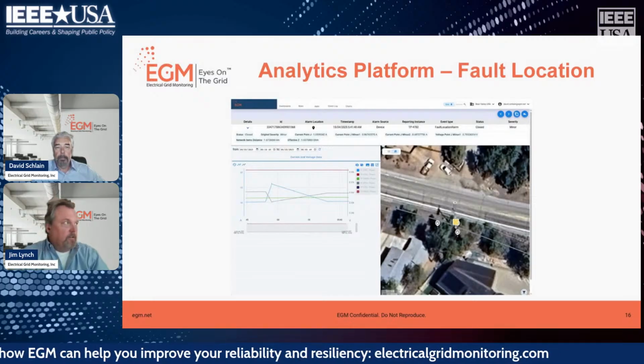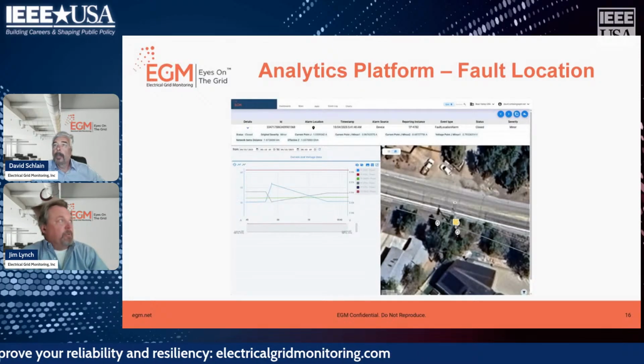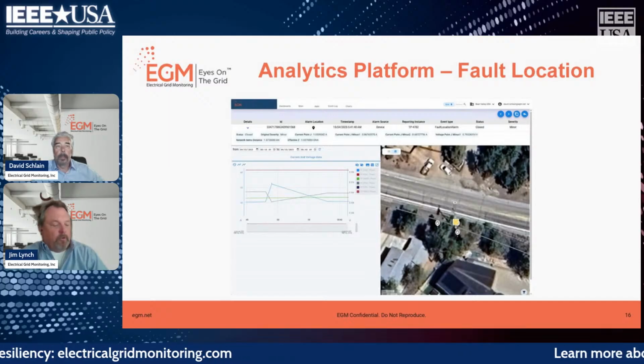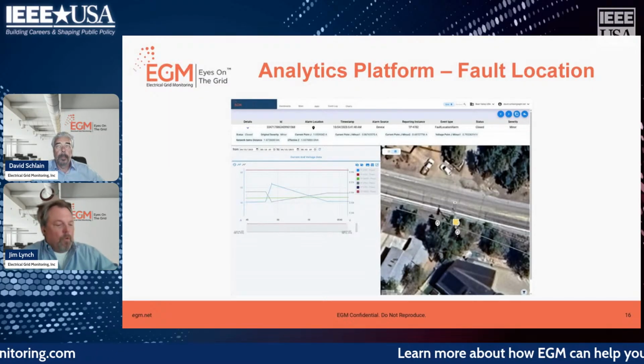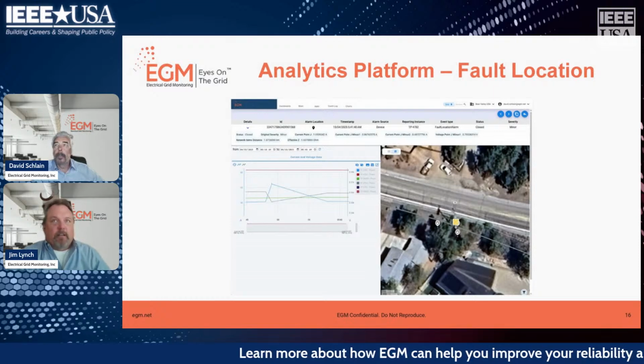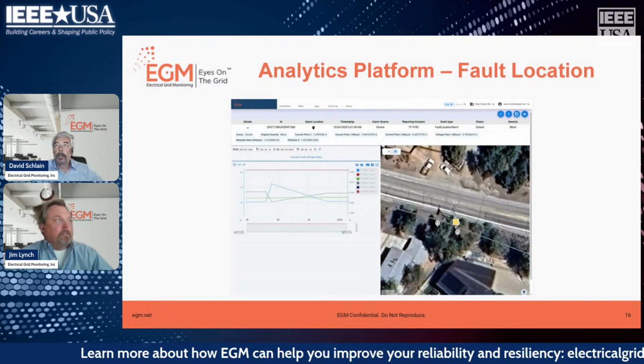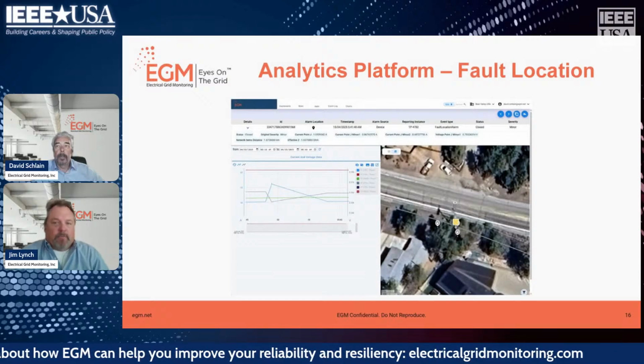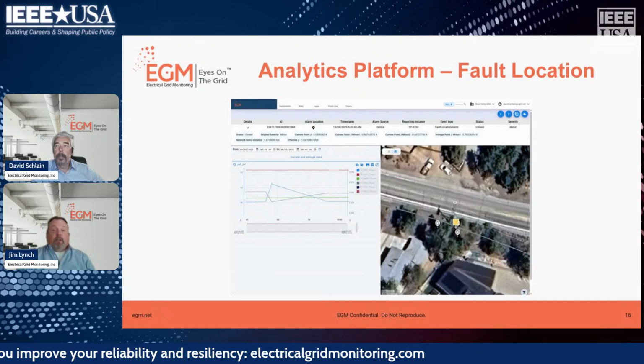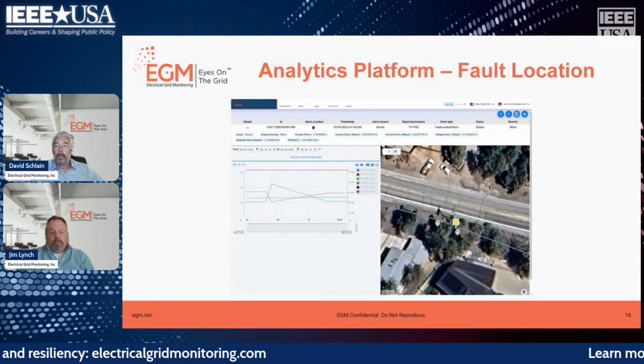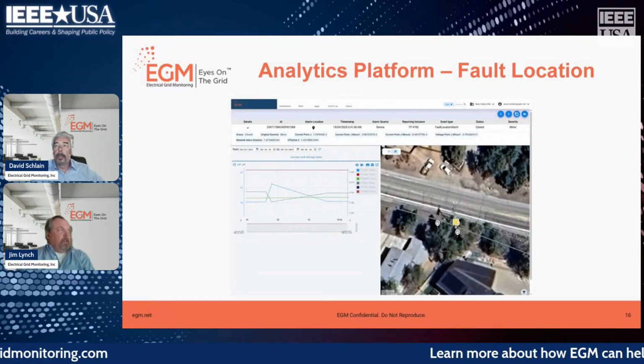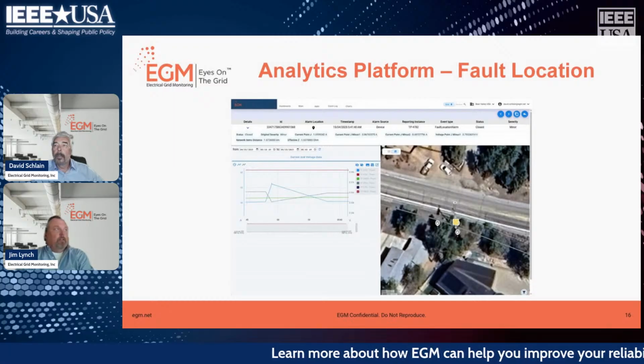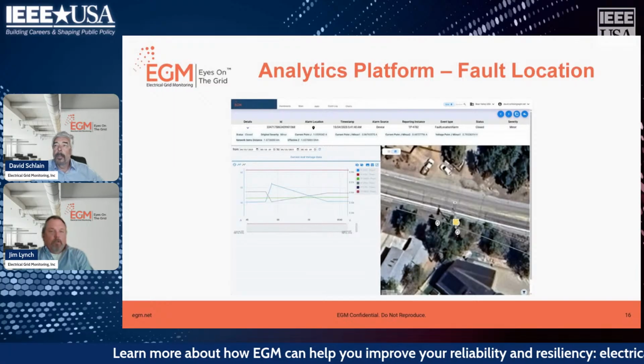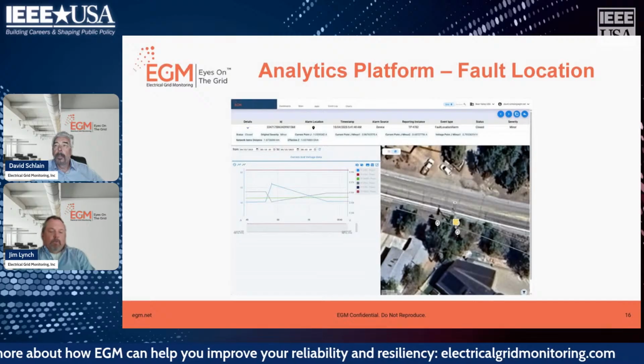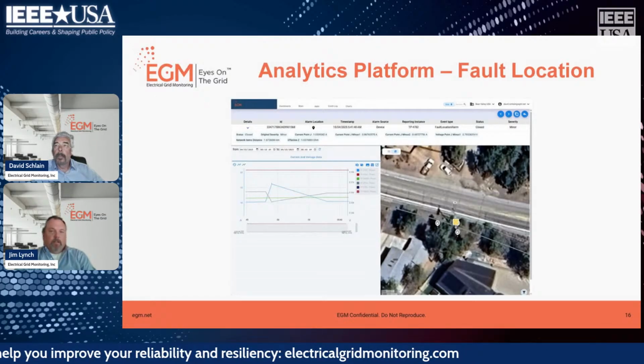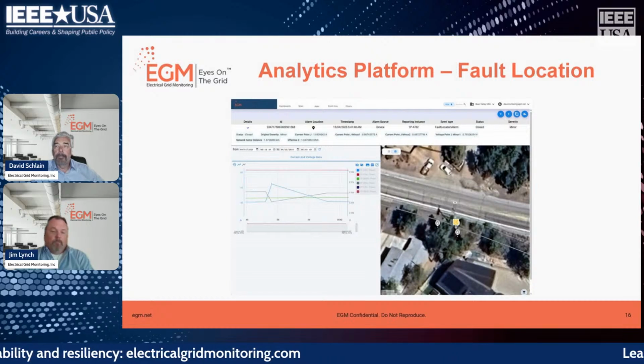I noticed in the chat, could galloping lines potentially have been detected in Spain and caused the outage there? Certainly, but without putting the system out there and seeing what the galloping lines looked like, their pattern, having sensors by themselves and this type of technology wouldn't have mattered. It's the function of collecting the data, analyzing it, and turning it into usable information. That pattern is then reused, and reused, and reused. So it's really more complex than just looking at a waveform - it's multivariate data. There's the waveform, and there's the wind that caused it.